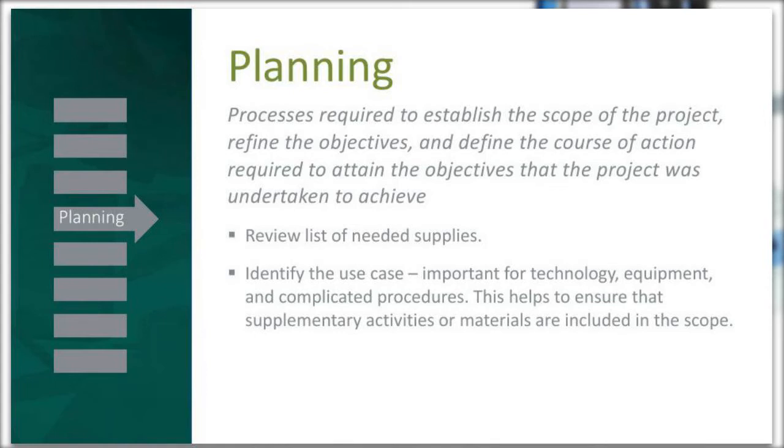We also make sure that we identify the use case. Now, when people say they want a centrifuge, we have to understand, can it be a fixed or a variable speed centrifuge? Is it going to have a max speed rotation or a minimal speed rotation? Are you going to measure it in G's or RPMs? Does it need to be standard or refrigerated? Can it have a fixed bucket or can they swing out buckets?